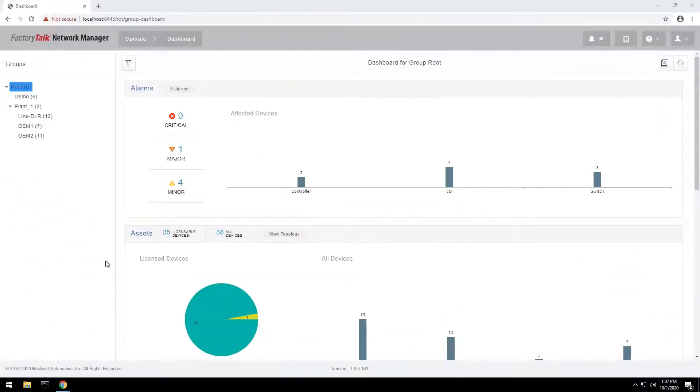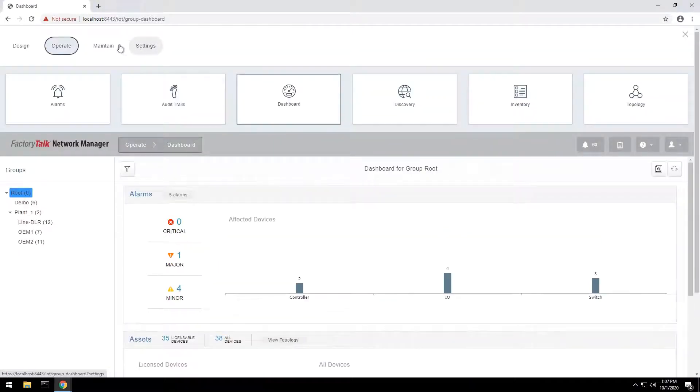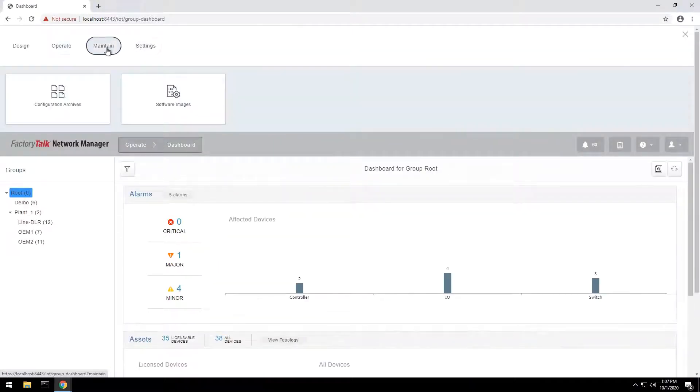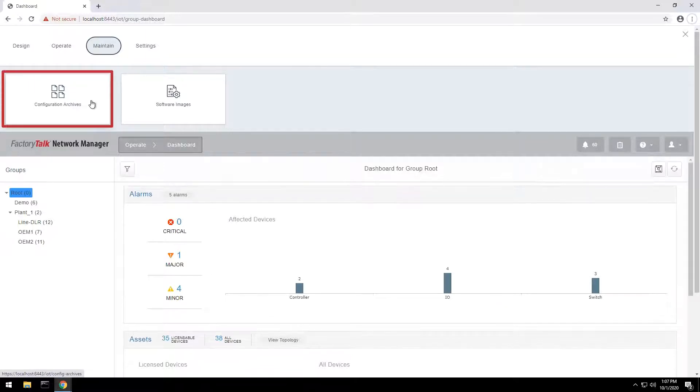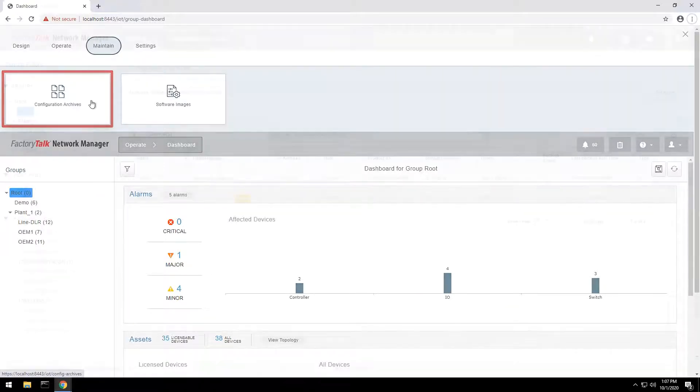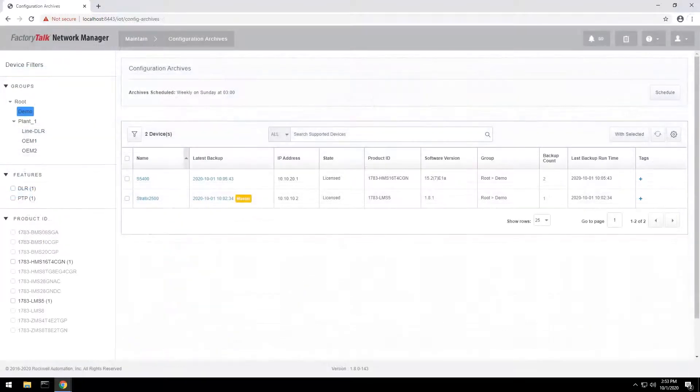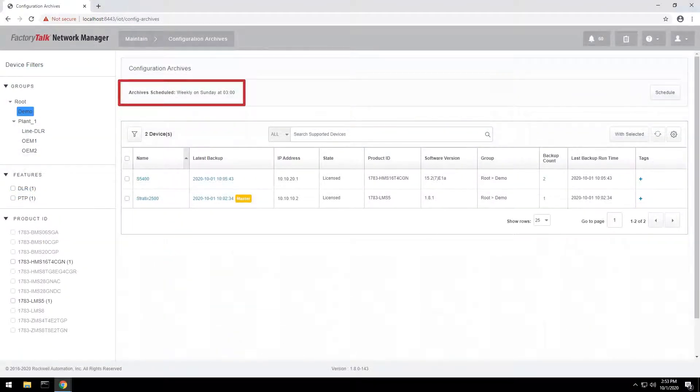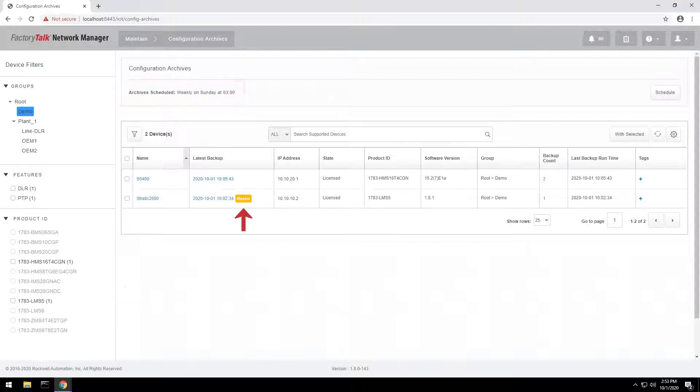To simplify switch configuration management, FactoryTalk Network Manager creates backups of switch configurations, allowing users to view, download, compare, and restore different versions. Configuration backups can be scheduled on a daily or weekly basis or performed manually. A known good configuration can be designated as the master copy. Up to 10 configuration versions can be stored in the database.